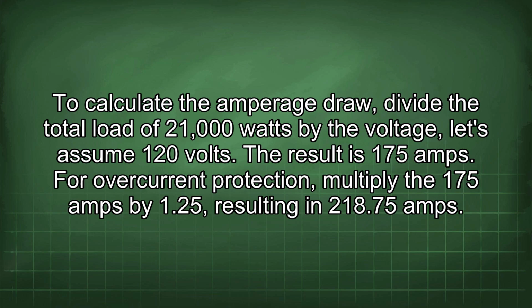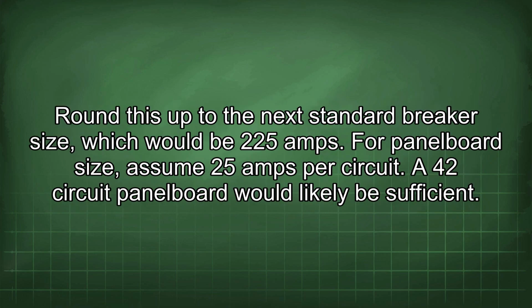For overcurrent protection, multiply the 175 amps by 1.25, resulting in 218.75 amps. Round this up to the next standard breaker size, which would be 225 amps. For panel board size, assume 25 amps per circuit. A 42-circuit panel board would likely be sufficient.